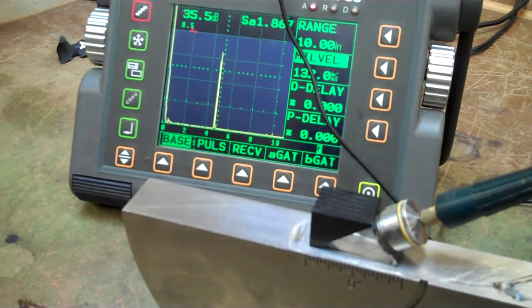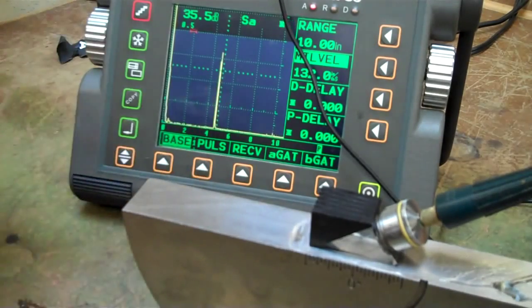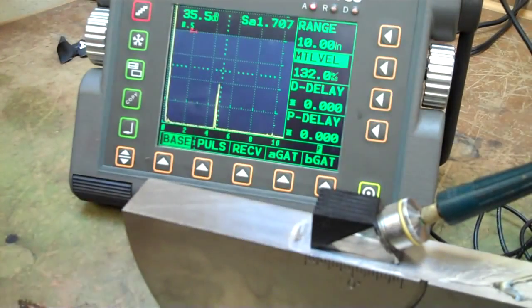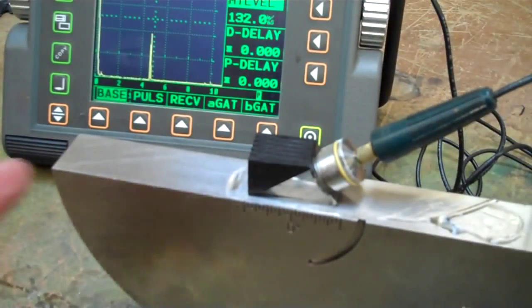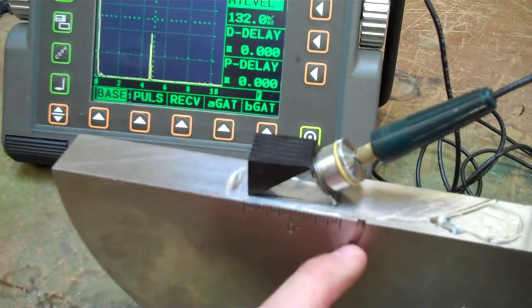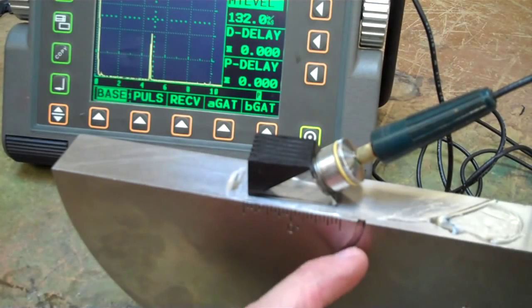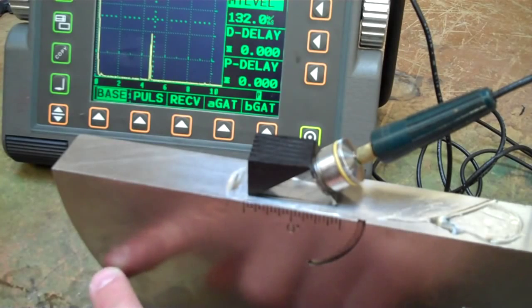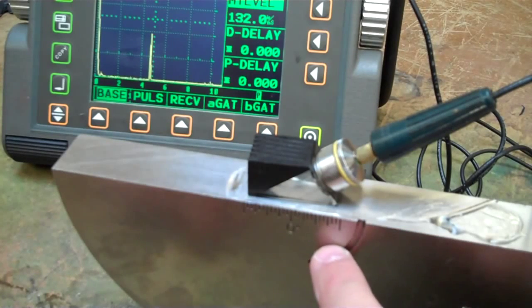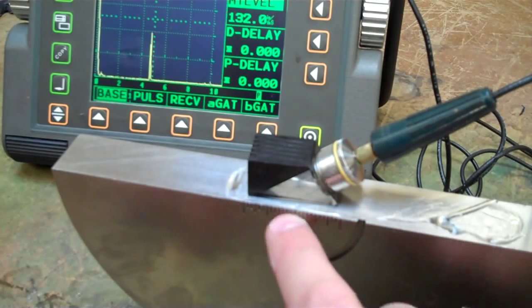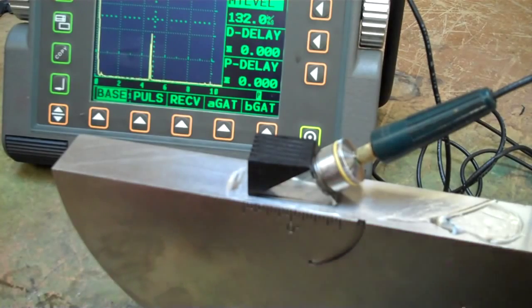Okay, part number 2. Verify the distance, or set the distance calibration up. Since we have a type 1 IIW block, we should see reflectors at 4 and 9. And we know that because here's our 4-inch radius, here's our 1-inch radius. Couple the two together, you're going to get a signal from a 4-inch. Some of that sound's going to bounce down here, come back, going to come down again, and we're going to get a signal at 4 and 9. So, let's do that.